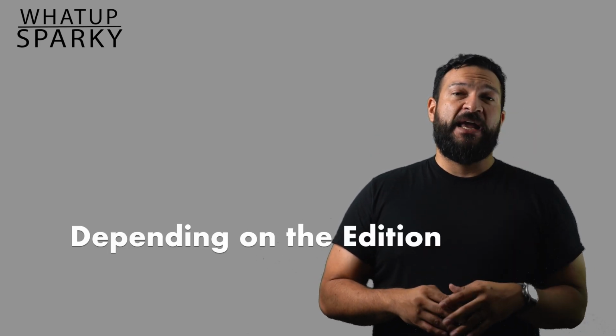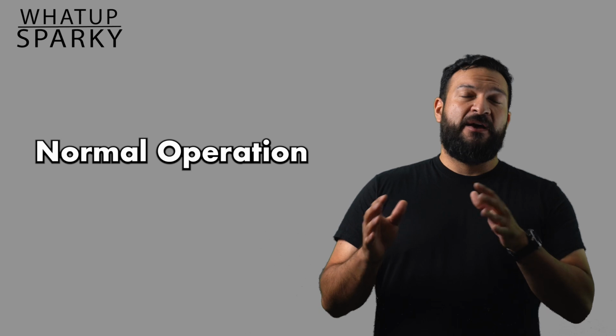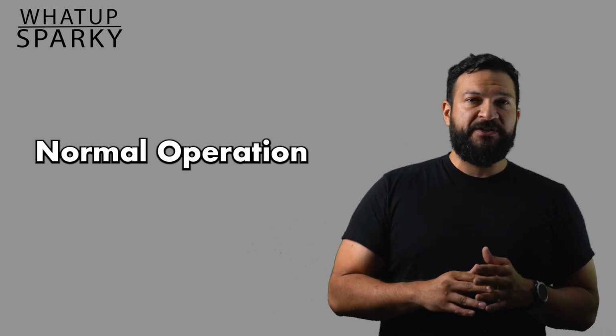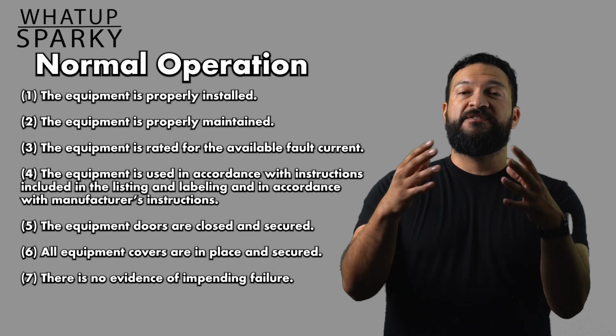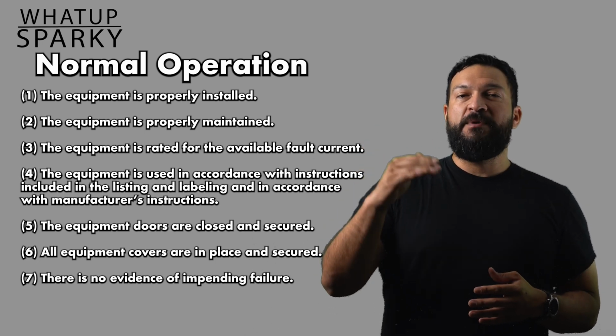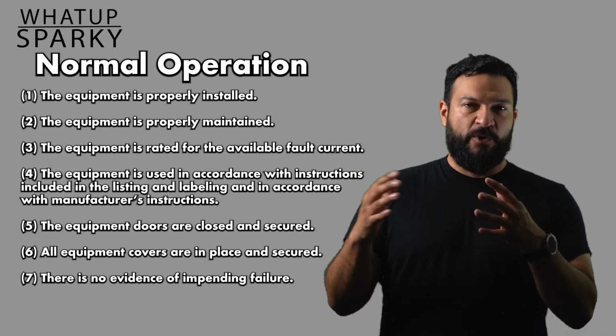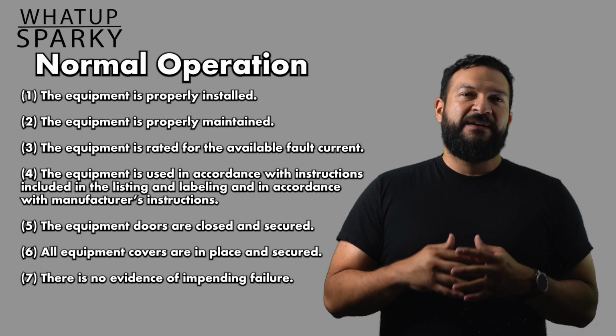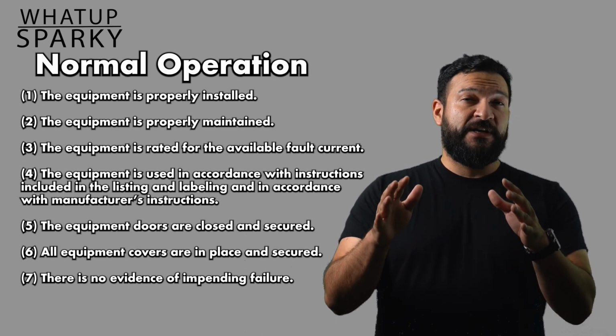There are some exceptions though, and they're not loopholes, they're more like guardrails, and right now there's 5 of them, and 2 of them are pretty close, so we're gonna talk about those 2 first. Now, the first one is normal operation. Now, this one's specific. Normal operation, this is a defined term that includes a list of requirements, but here's the key. If the equipment meets all of those conditions for normal operation, using it doesn't even count as energized work.